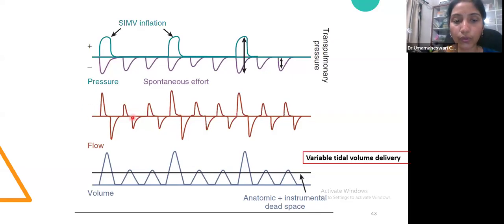So this is the flow graph, the same. And you can see here that there is a variable tidal volume depending on whether there is a spontaneous breath or whether it is a supported breath. So I repeat again, SIMV supports only the set rate, whatever you have set. Say, for example, you have set a rate of 40, baby is breathing at a rate of 60. The machine will support around 40 breaths, provided that they are falling under the trigger window. And the remaining 20, the baby will take breaths, but they will not be supported by the machine.